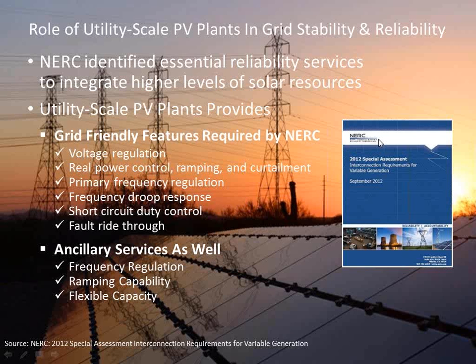Now, when we started this exercise about 6-7 years back, we had to work with them to establish faster communications and the ability to respond much faster than they had required in the past. The fact that we have control loops of 100 milliseconds means the inverter has to be able to receive that signal and respond to it. So that part of the specification is met by only a small subset of inverter manufacturers, but other than that, the specs are pretty generic.